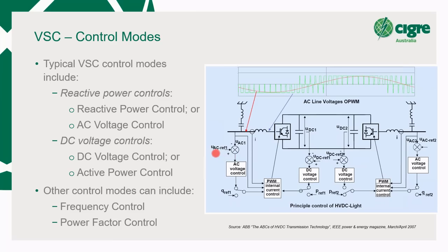where it shows it's got a reference from the operator, it's measuring the AC voltage, and it's going into this AC voltage control. Alternatively, you can flick this switch and you can just type in your own Q value. And all of that goes into the overall internal current control, which will cause the converter, as I mentioned, to create an AC voltage waveform of the right amplitude. So they're the two options. And in this example, both ends are sitting in AC voltage control.